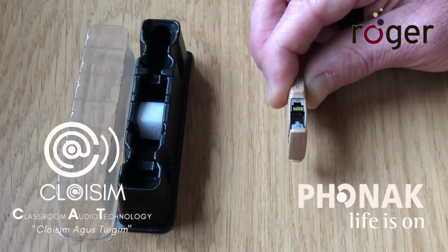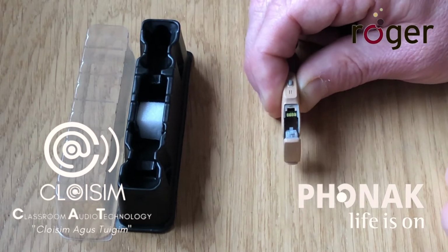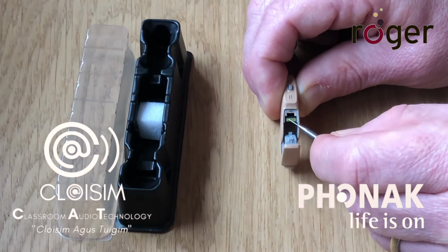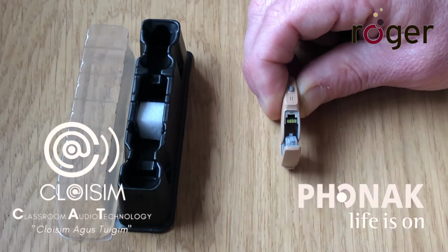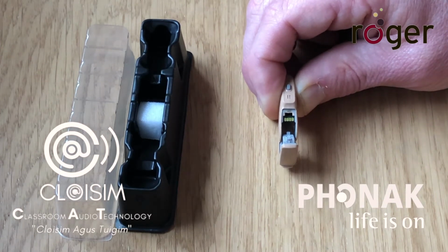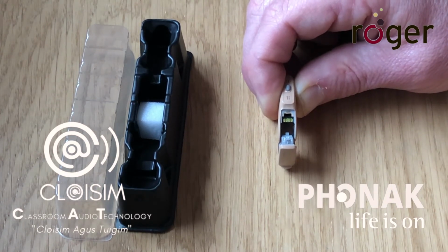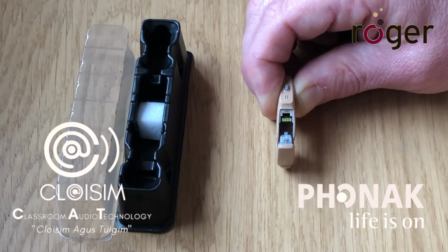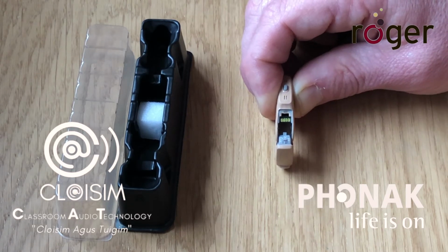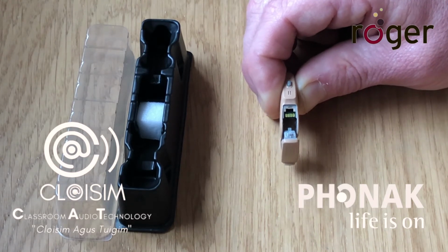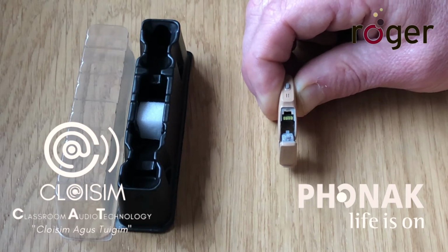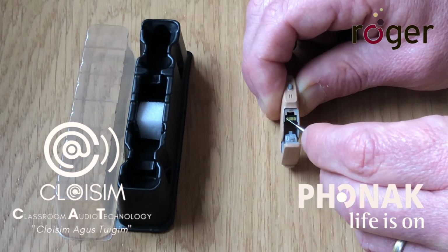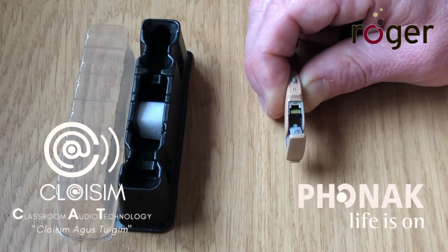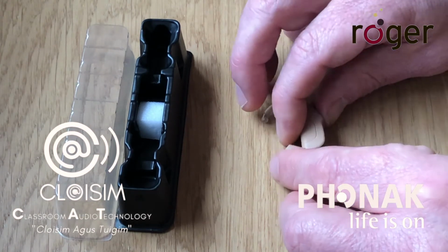They are very important. The reason I'm mentioning them now is that often on new hearing aids, manufacturers will put a white strip across these bars to cover them. Because if the hearing aid is being used outside of education or outside of Roger, then these contacts will not be needed. So that strip is used to protect from corrosion. We will always look to have this cover taken off. Always remember, when you put your receiver on, first make sure that you can see those four brass contacts. Once you've done that, you're ready to insert the battery tray, the battery.